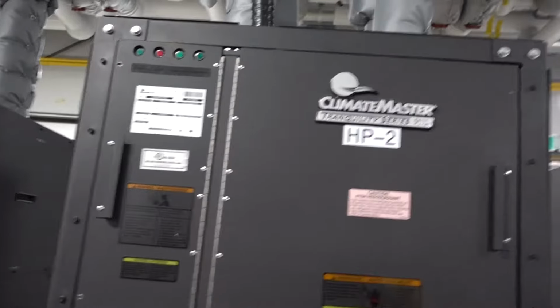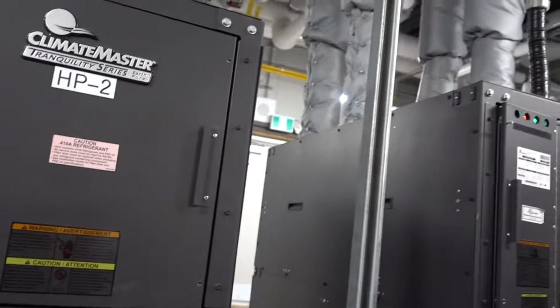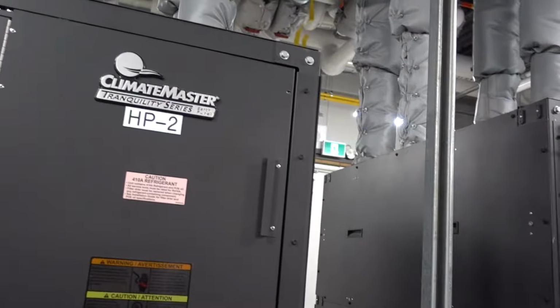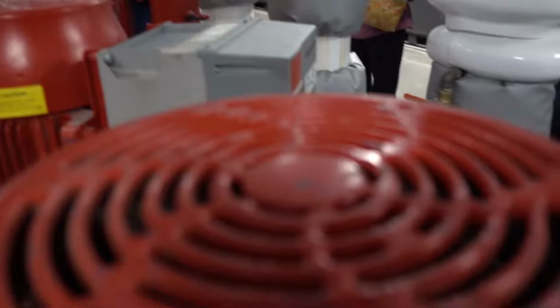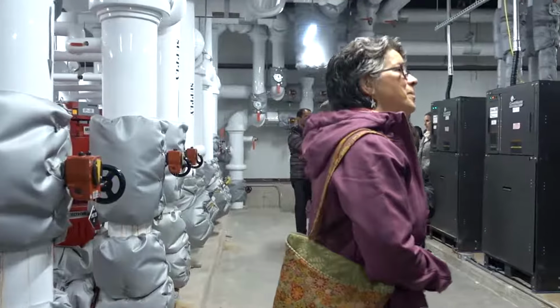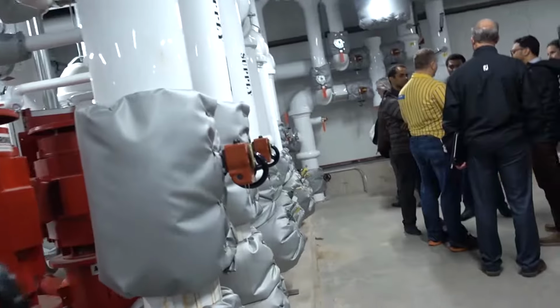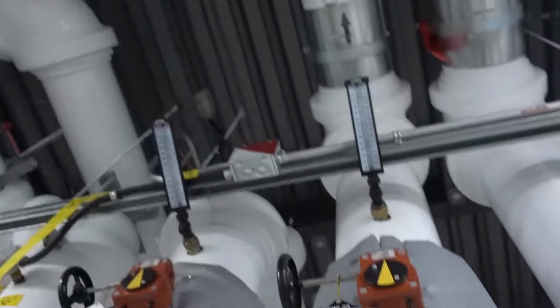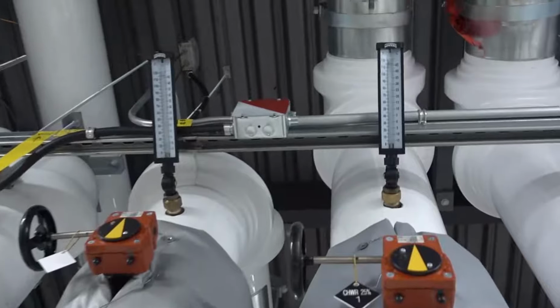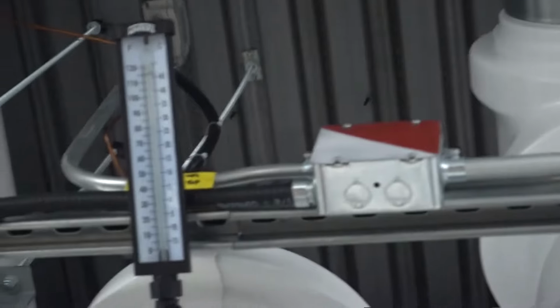As most of you have inferred, these are the heat pumps. Two compressors per unit gives me two-stage, 12 stages overall. Over on this side are the variable frequency pumps that feed the water through the various loops. For example, to the ground, up in this room is a short heating loop as well as a short cooling loop. Then in the building itself are the much longer building heating and building cooling loops. And then finally, there is the geothermal to fluid cooler exchange.